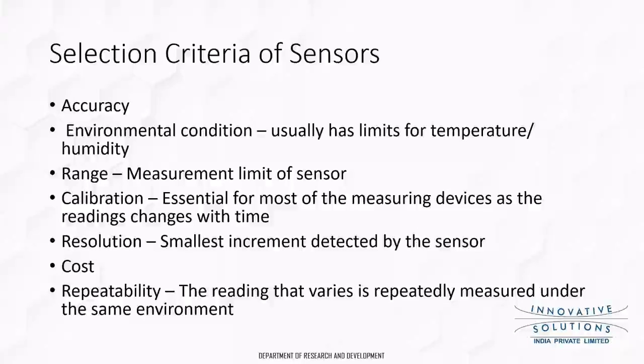Then we need to understand the environmental conditions. Suppose you're working in an open environment with temperature sensors all around, and there is rain or it is a humid environment like Mumbai. In such cases, ordinary sensors can get damaged very easily because they are not made for that environment. So we need to understand what environment the sensor is designed for. It can be the IP protection, the current capacity, or the shielding. We need to consider the environmental conditions while selecting the sensor.